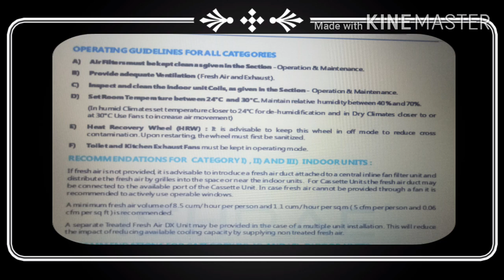So what is the recommendation for category 4, 5, 6 indoor units? Fresh air must be provided by inlet duct and fan. It is advisable to provide MERV 13 or higher filters fitted on the air handling unit. If a higher filtering capability is retrofitted into an existing system, care shall be taken to ensure that the fan and motor capacities are adequate to handle the higher pressure drop.